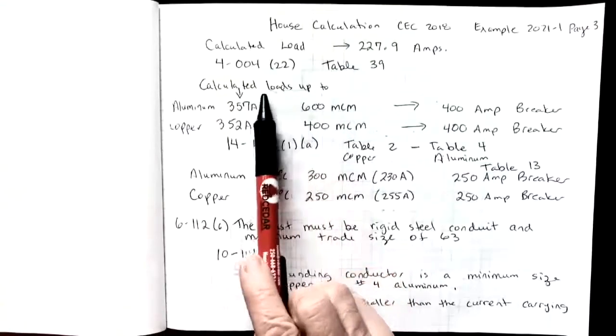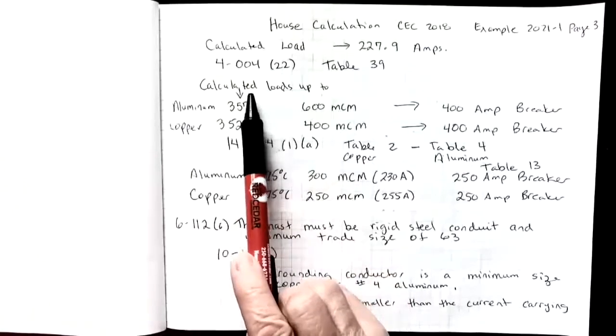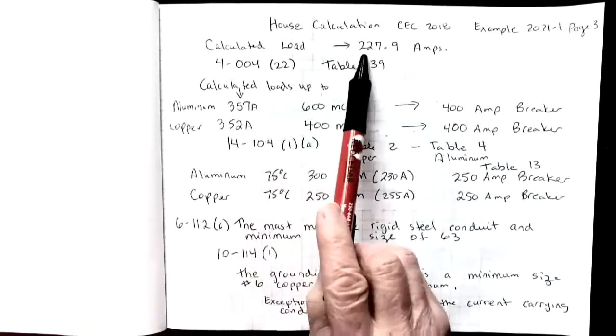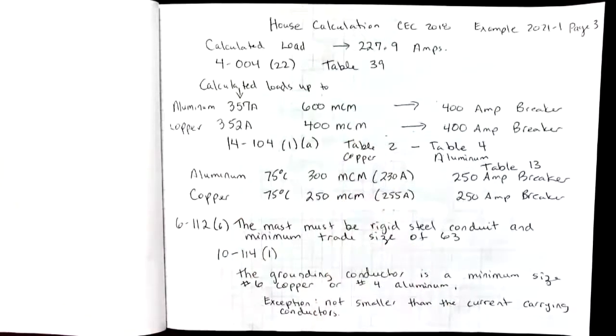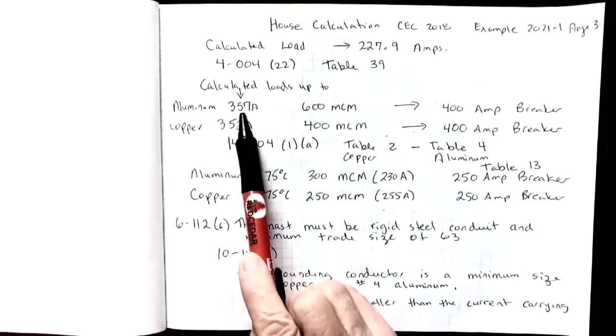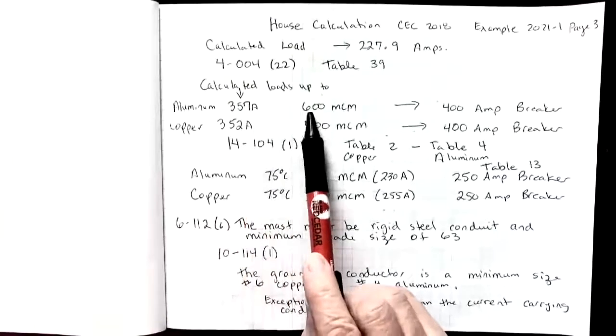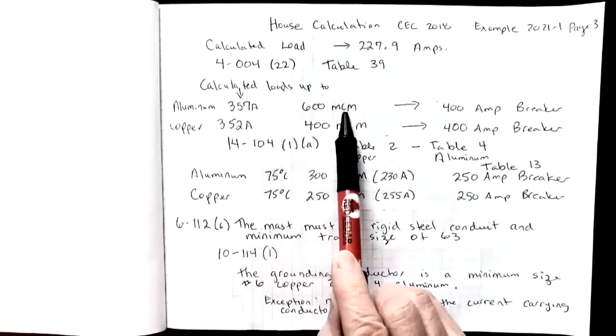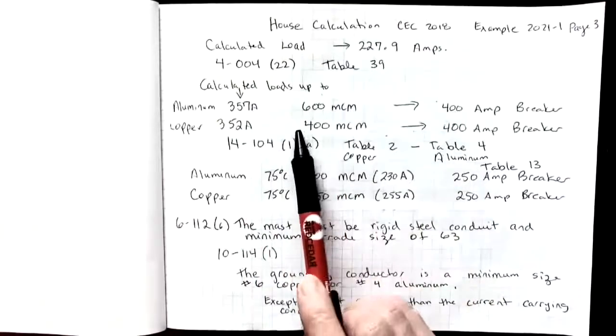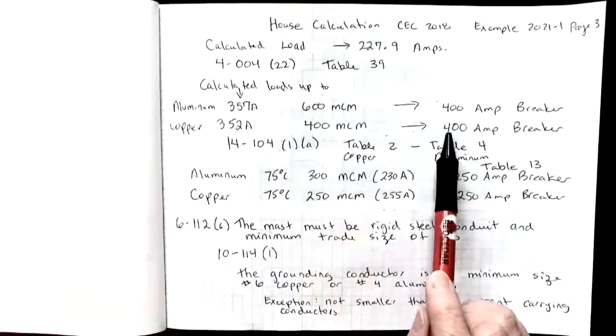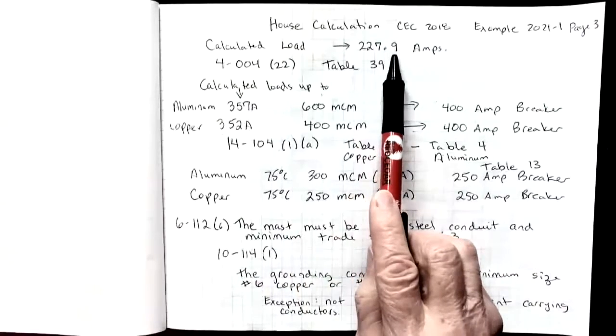In table 39, what they do is give you a calculated load column. So you look in that calculated load column for a number that's greater than your actual calculated load. For aluminum, I would have to go to 357. For copper, I'd have to go up to 352. That forces me to use a 600 MCM size aluminum wire and a 400 amp breaker or 400 MCM copper wire, still a 400 amp breaker. Now my load was only 227.9.